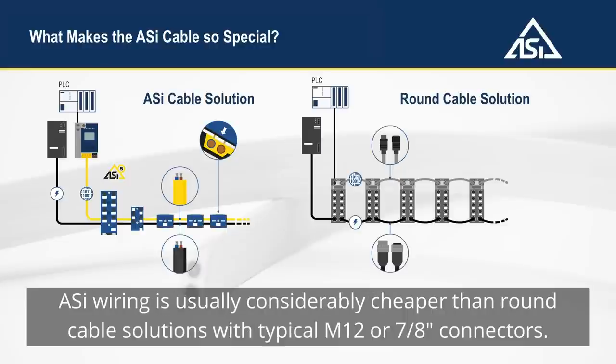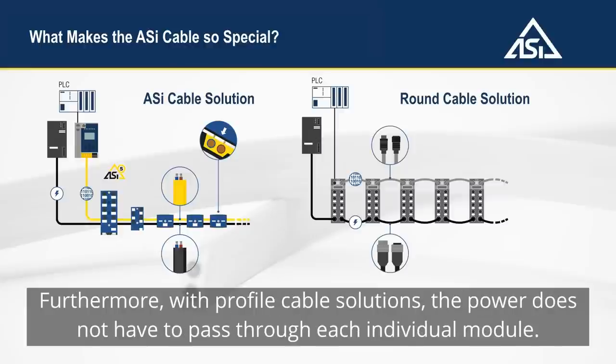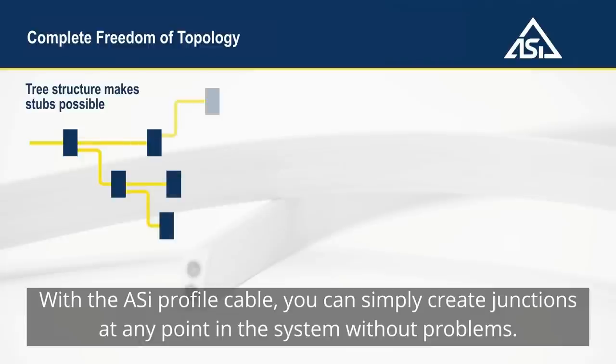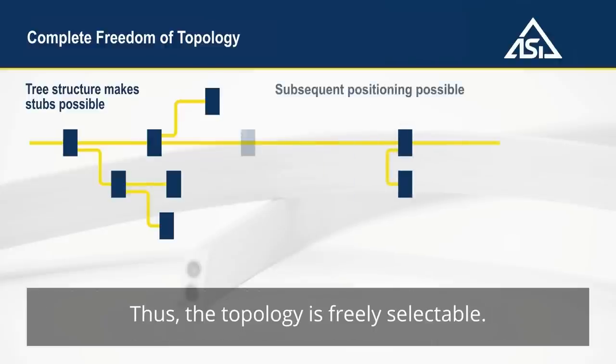ASi wiring is usually considerably cheaper than round cable solutions with typical M12 or 7-eighth inch connectors. Furthermore, with profile cable solutions, the power does not have to pass through each individual module, so no power loss occurs. With the ASi profile cable, you can simply create junctions at any point in the system without problems. Thus, the topology is freely selectable.